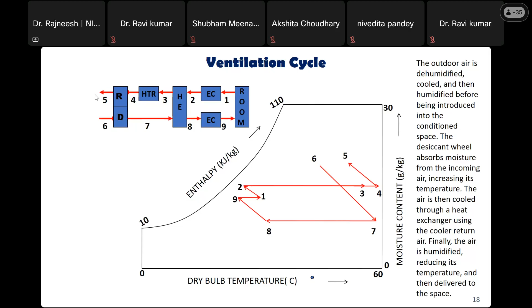So the outdoor air is dehumidified and cooled. That is basically the purpose of any air conditioning system. And then it is humidified before being introduced into the conditioned space, with the help of the additional evaporative cooler, as I mentioned. So the desiccant wheel absorbs moisture from the incoming air, increasing its temperature. A little bit of temperature is increased because the moisture has been taken up from the air. The air is then cooled through a heat exchanger using the cooler return air. Finally, the air is humidified, reducing the temperature, and then it is delivered to the space.